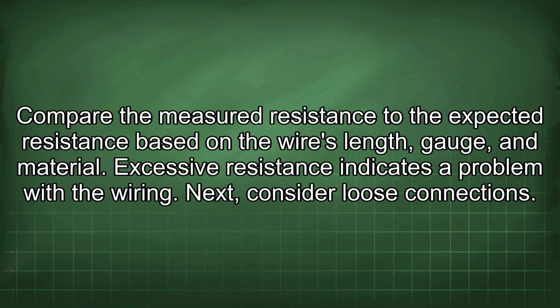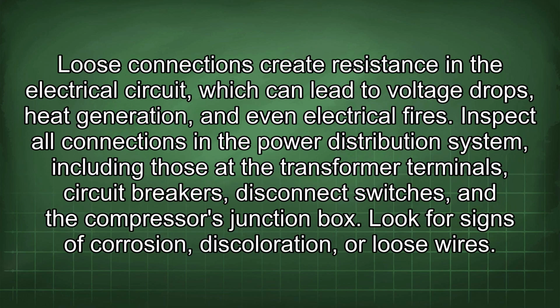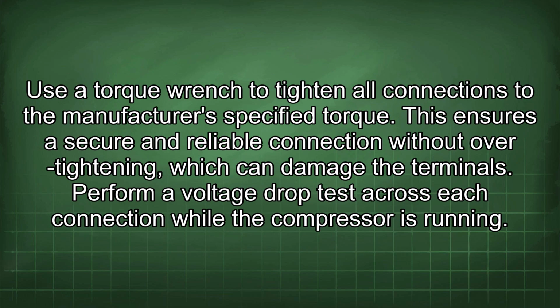Next, consider loose connections. Loose connections create resistance in the electrical circuit, which can lead to voltage drops, heat generation, and even electrical fires. Inspect all connections in the power distribution system, including those at the transformer terminals, circuit breakers, disconnect switches, and the compressor's junction box. Look for signs of corrosion, discoloration, or loose wires. Use a torque wrench to tighten all connections to the manufacturer's specified torque. This ensures a secure and reliable connection without over-tightening, which can damage the terminals.